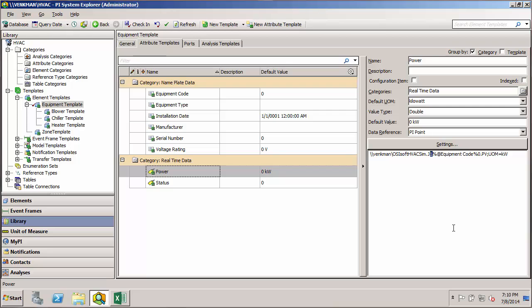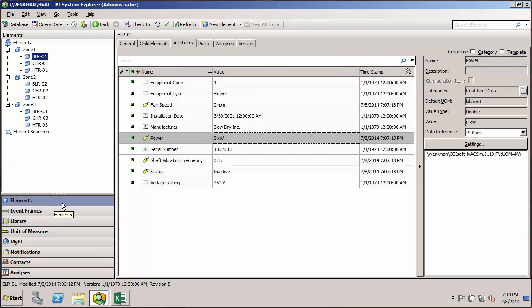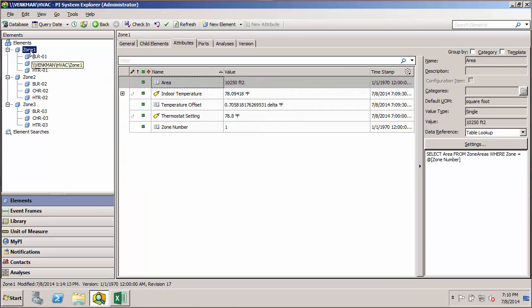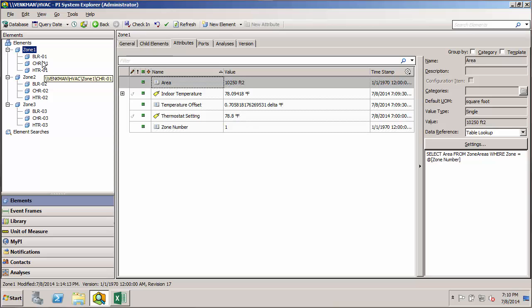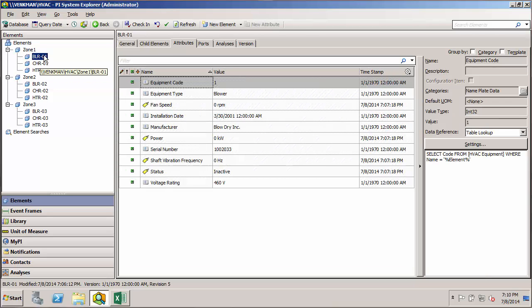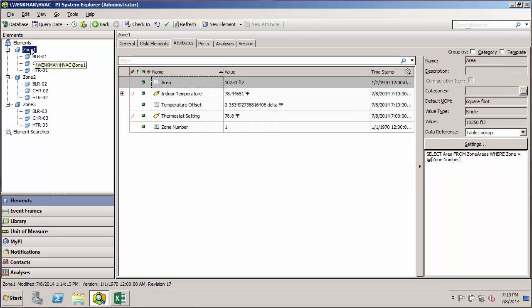The next thing we need is the zone number. Here's where we need to learn something new. If we jump back to our elements and look at our hierarchy, our equipment elements don't have an attribute called Zone Number. But just above them, at the parent level for Zone, we do have a Zone Number attribute. So we need to figure out a substitution parameter that lets us go from the equipment element level up to the parent element level — the zone level — and pull out the Zone Number attribute value.